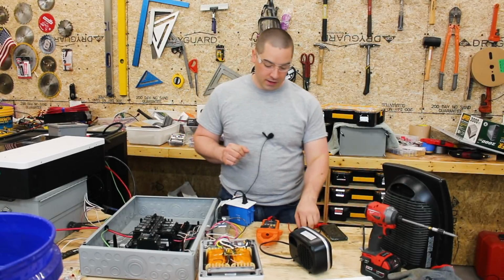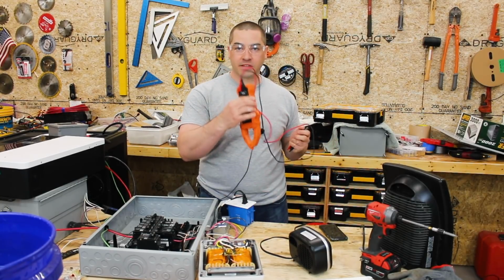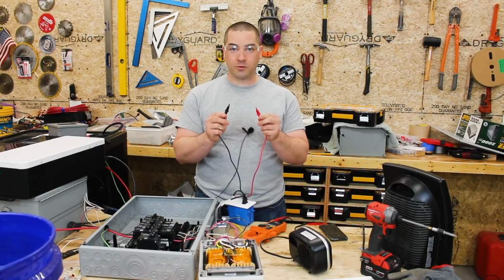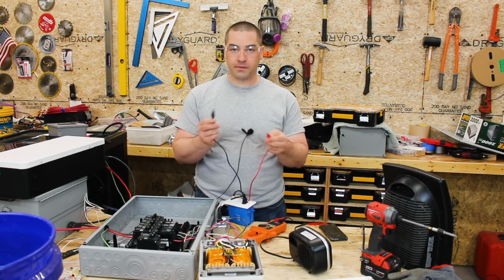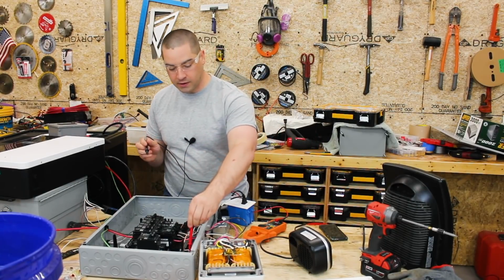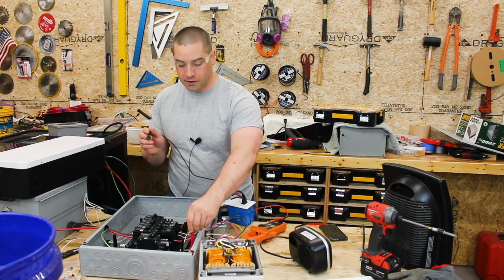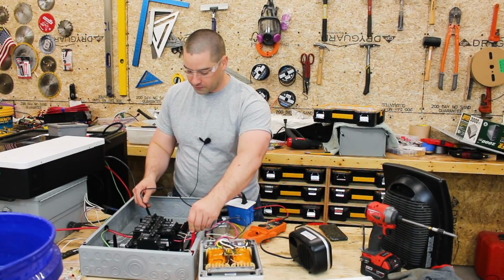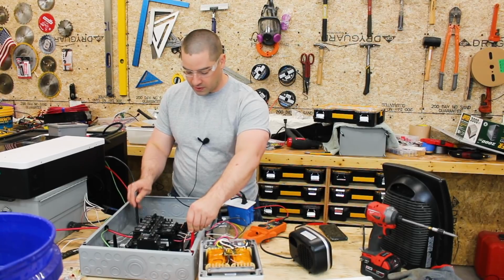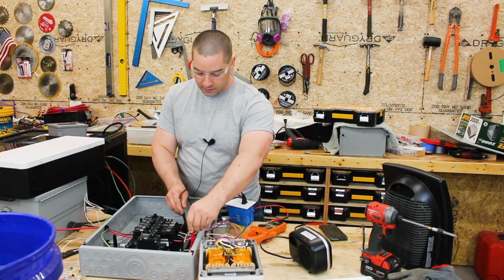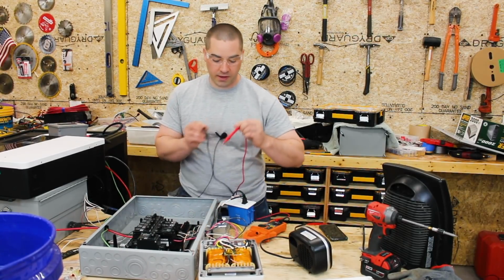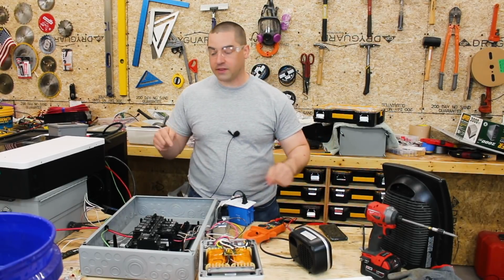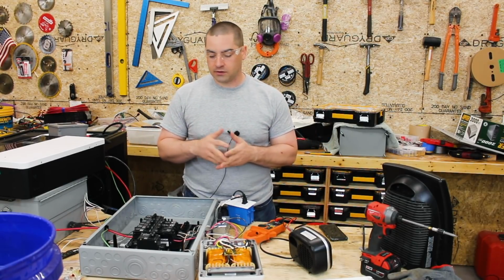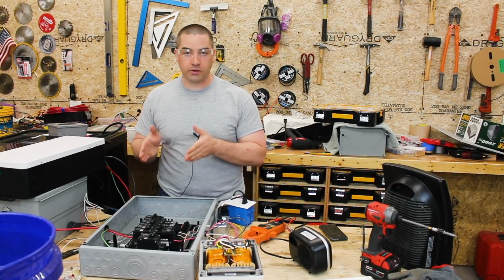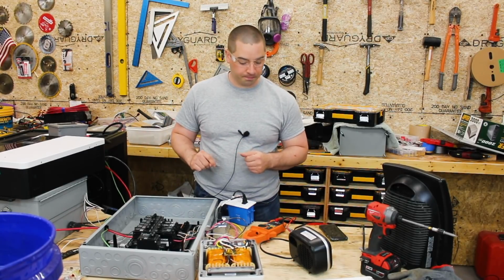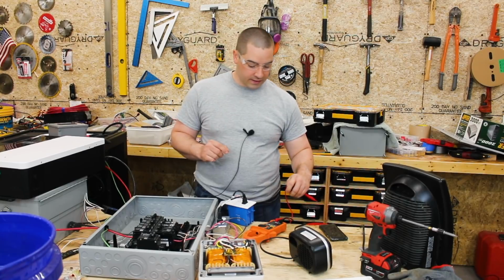Right now I have my multimeter here. If there's continuity between the two probes, we'll hear a beep. So now I'm going to check between the grounding bar and any neutral. There's four neutral points in here, and I'm not getting anything for them. That means we will have to add the screw to do the neutral to ground bond inside the panel.